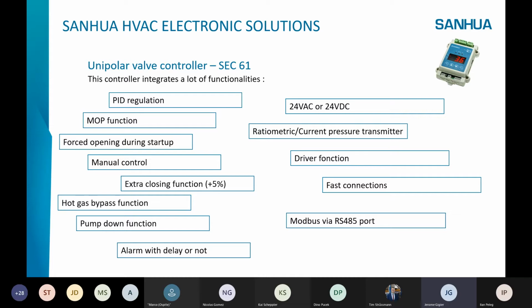And we have alarm with delay or not. So we have an output relay, normally closed or normally open, on the controller. This controller needs to be supplied with 24 volts DC or AC voltage. We can use ratiometric, so it's a voltage or current pressure transmitter, and we can use also for driver function.